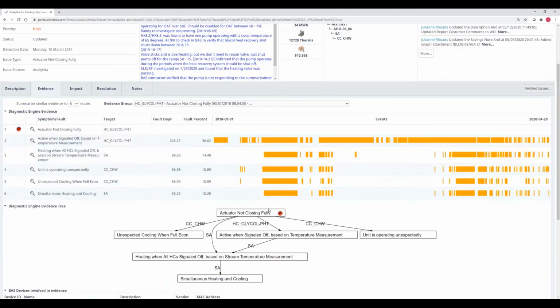This is the output of our automated fault detection. Our system said, hey, these five things are happening at the same time, and down here is the logic flow diagram showing these things are happening, therefore the result we've determined is simultaneous heating and cooling. So this all happens automatically and gets served up to the customer and our analysts in-house.